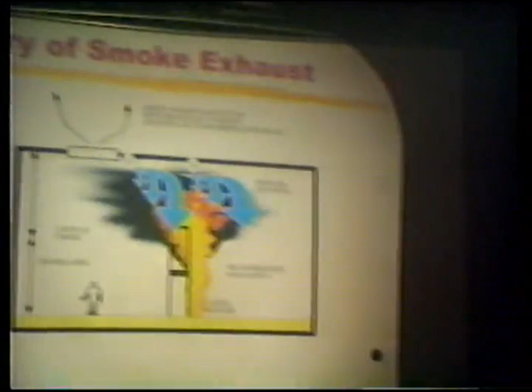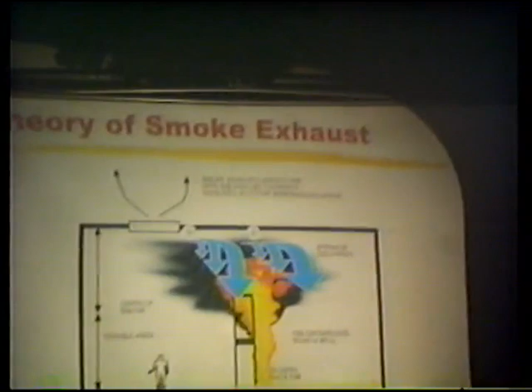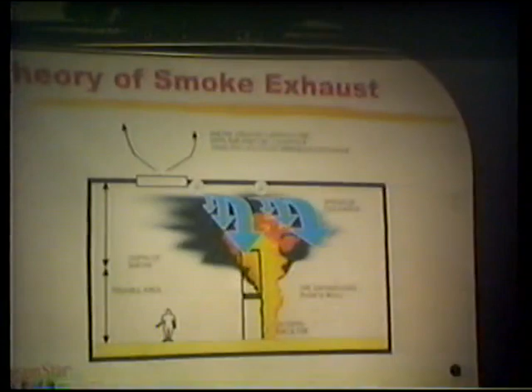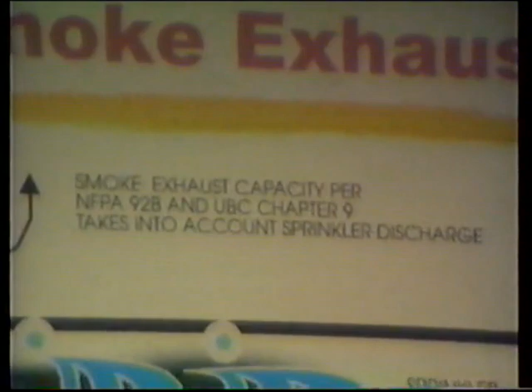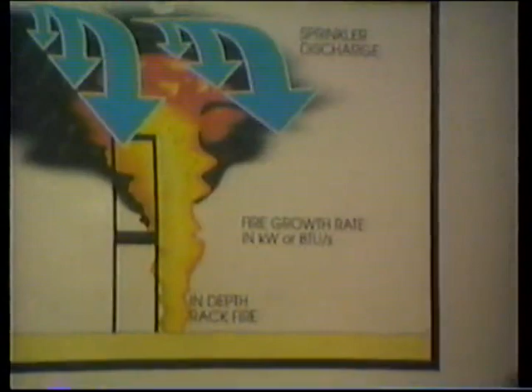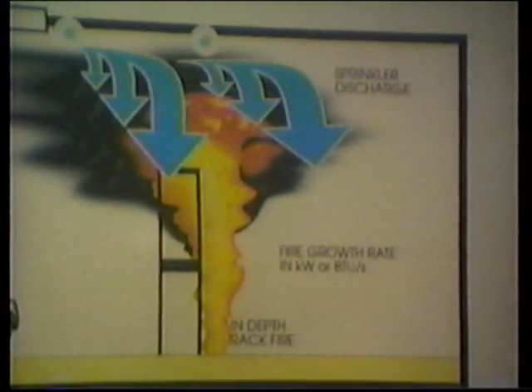You can use it with smoke exhaust. You can take this, and whether it be something like high-piled storage or even an atria, you can come up with a design basis fire for that space, approximate when the sprinklers will discharge, and design your entire smoke control system around that. Code today tells you that you can design your smoke control system and assume that the fire won't grow any further when the sprinklers discharge.